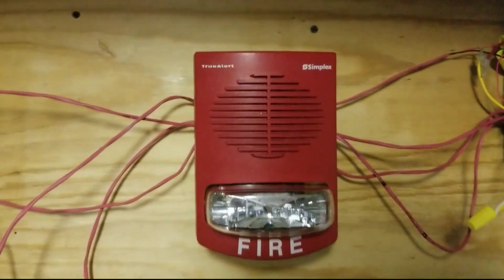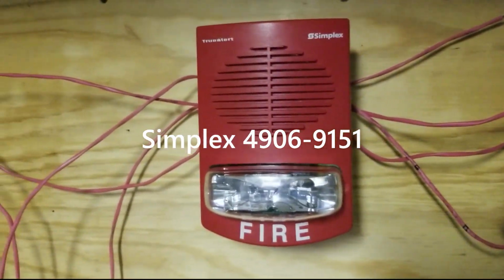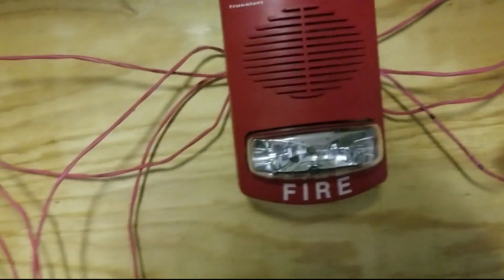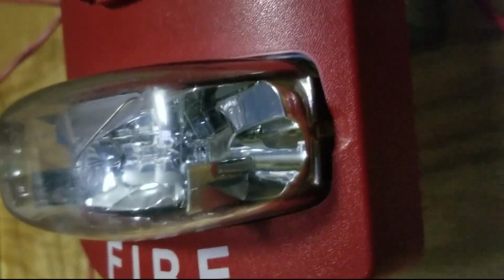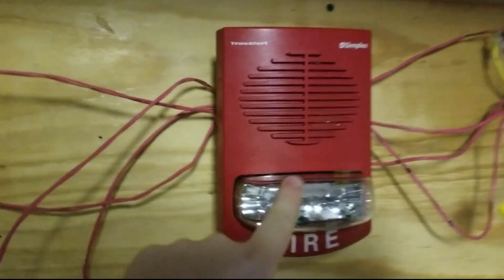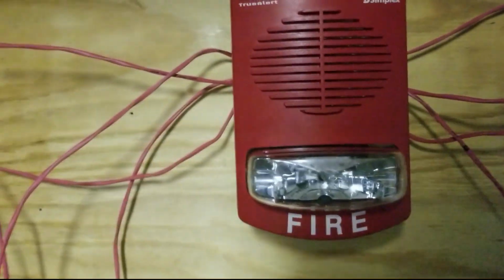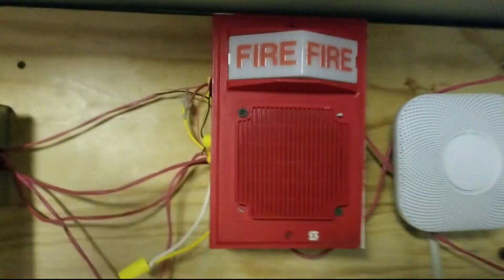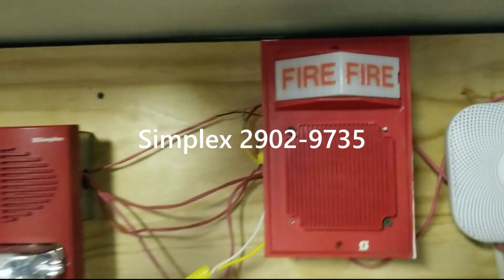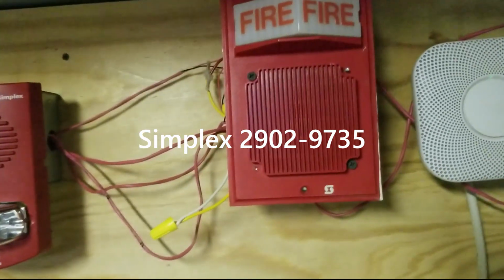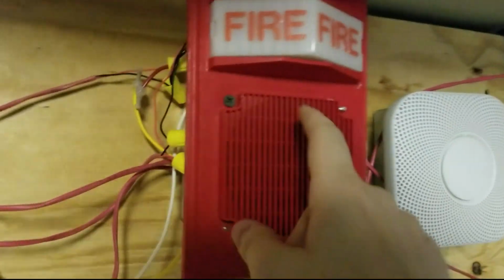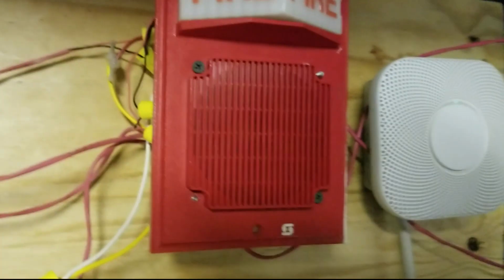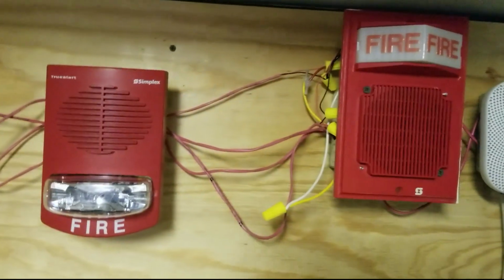For the first device, I have my Simplex 4906 True Alert speaker strobe. It's smart sync only and multi-candela, and I have it set to 30 candela. So this is on NAC 3 with the smart sync devices. Next to it, I have my Simplex 2902 speaker light combination. And this actually, instead of having an alarm behind it like I normally would, has the speaker that it came with. So both of these will be playing the voice evacuation message.